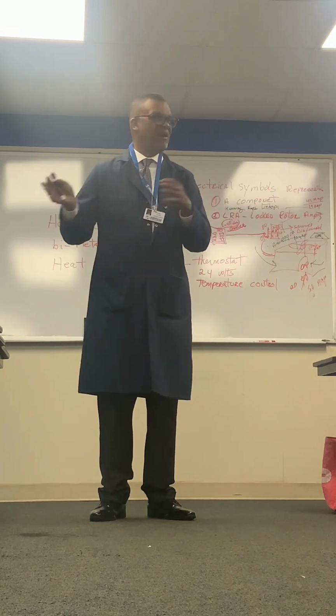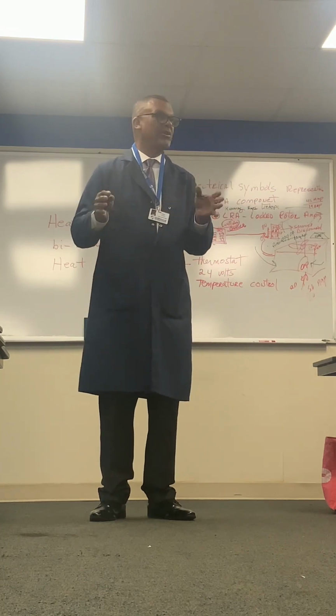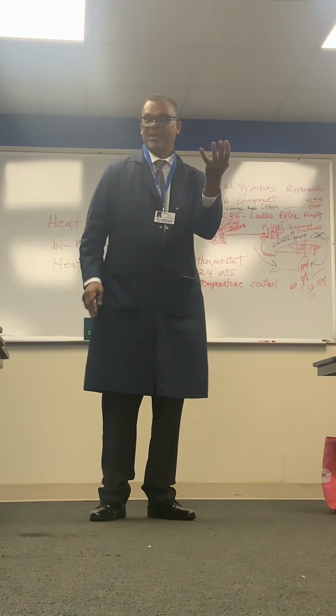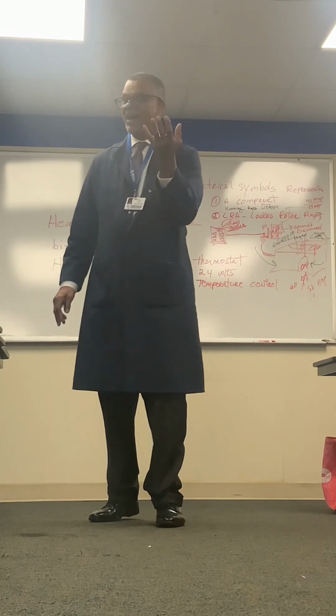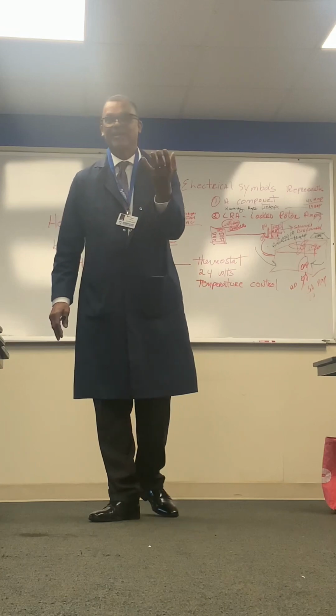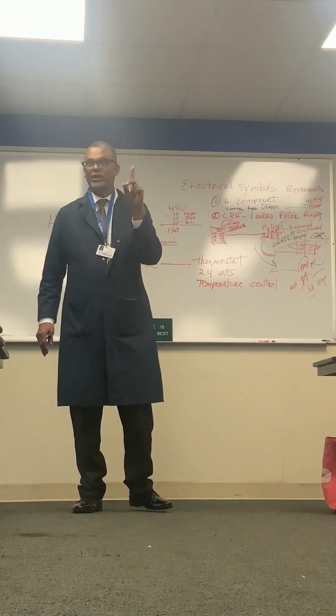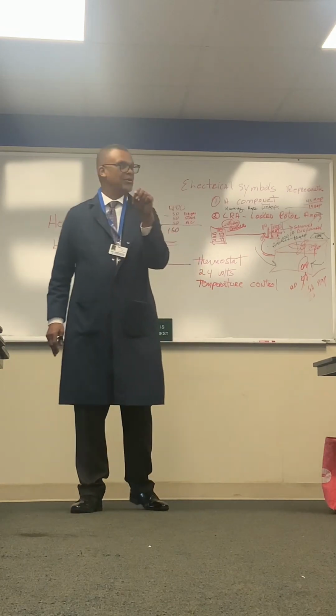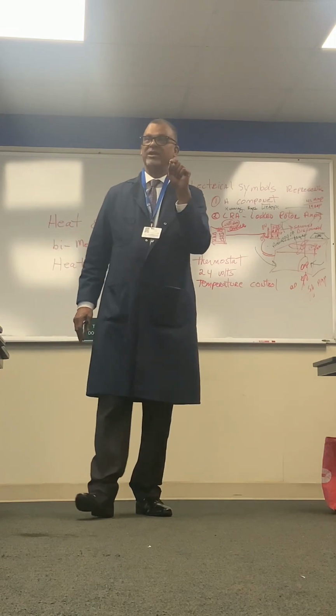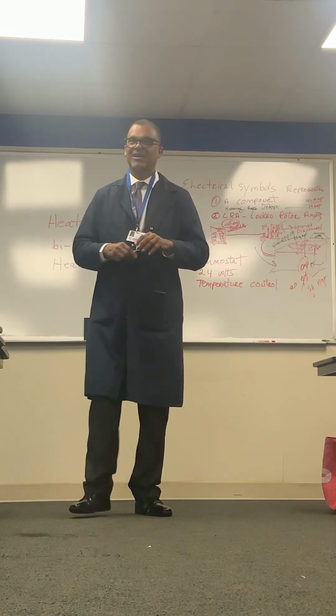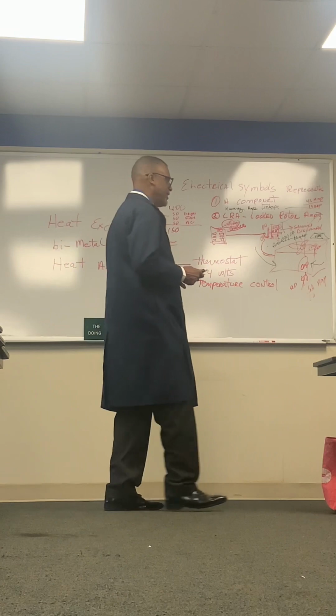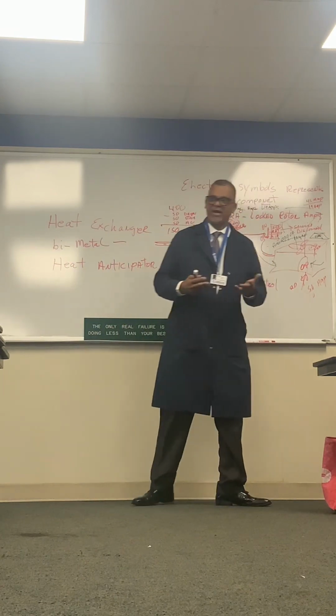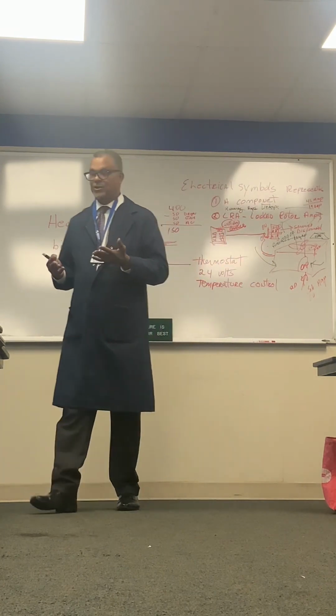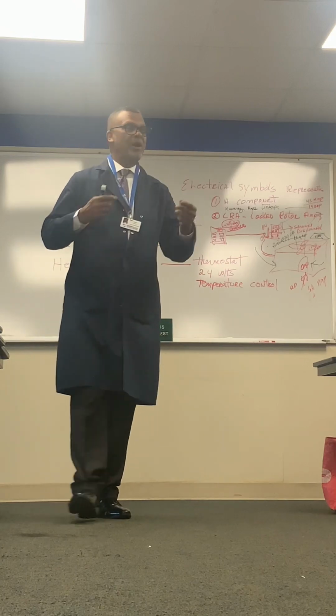It could be wired on that side so you don't have to carry all those different transformers. We used to have to carry all of them, different kinds of transformers. A multi-tap means, hey buddy, you can wire this up five different ways and it'll work. You only need one, as long as the VA on it is correct. What is VA? There you go. I don't have to write that down. Voltage amps.